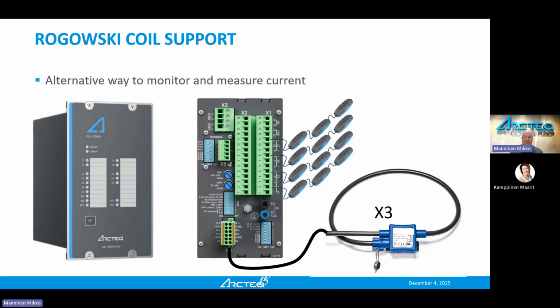Rogowski sensor in this slide here. This is an example of the low voltage Rogowski sensor, Rogowski coil. Both names can be found. We need one of these for each of the three phases, and it can be connected to this terminal block here. All the settings are always in the AQ100 series. It's a very easy and simple approach. Practically, you set up these dip switches according to design, and when you are done with that, you can press this one button here and auto configure everything.